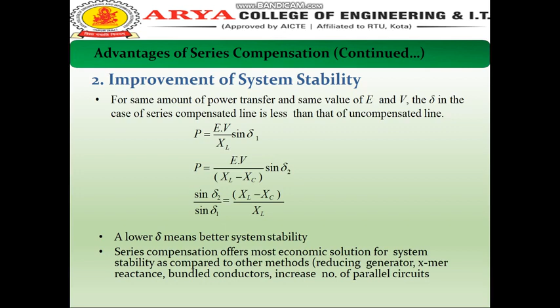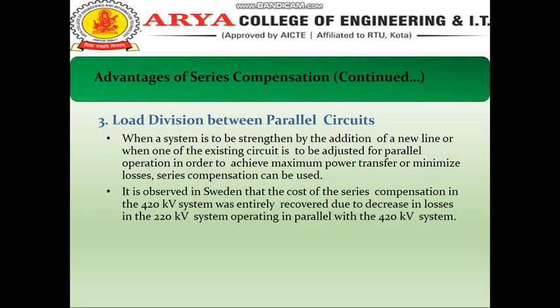Third, load division between parallel circuits. When a system is to be strengthened by addition of a new line, or when one of the existing circuits is unsuitable for parallel operation, series compensation can be used in order to achieve maximum power transfer or minimize losses. It is observed that the cost of the series compensation in a 420 kV system was entirely recovered due to the decrease in losses in the 220 kV system operating in parallel with the 420 kV system.